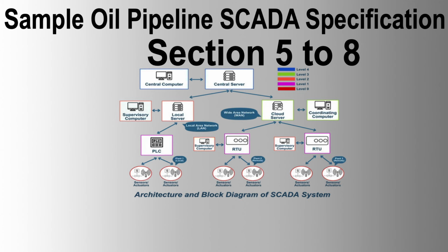7.8 Database software interfaces. 7.8.1 Real-time database. High-performance memory-based design for concurrent real-time SCADA functions. All access based on structured query language, ANSI SQL 92 commands. SQL access possible from seller-supplied programs and custom user-written programs using C, C++, and Java. Graphical user interface for direct interactive user queries. Access restricted by user logon privileges.